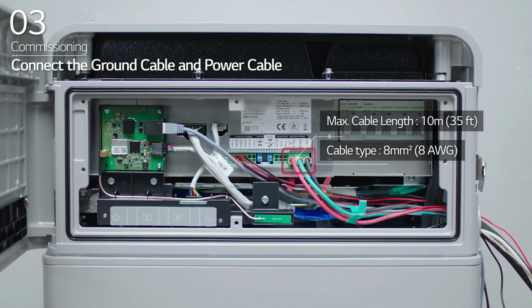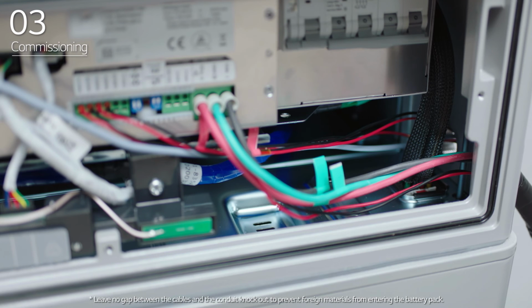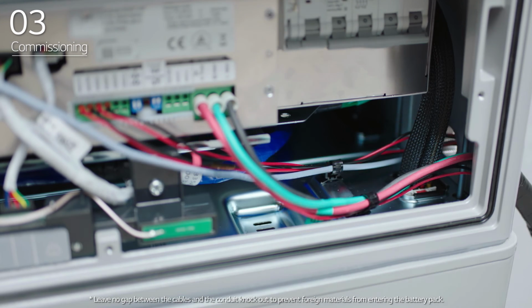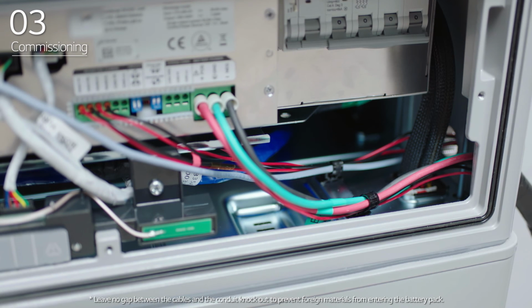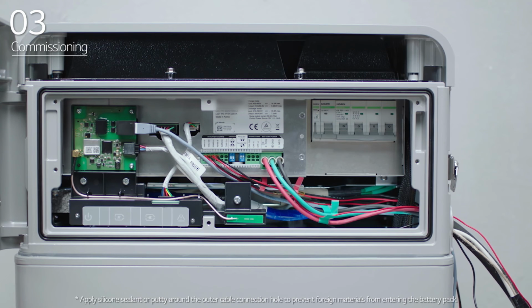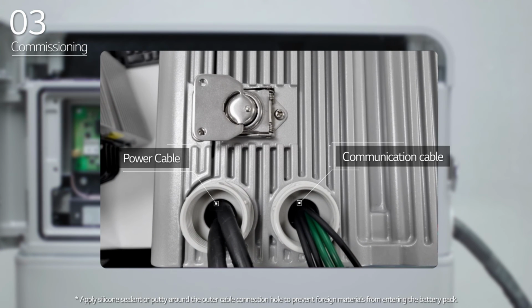Next, move to section E. Connect the ground cable and power cable. Arrange the power cables and communication cables separately using cable ties. Then, apply silicone sealant or putty around the cables at each hole to prevent foreign materials from entering the battery pack.